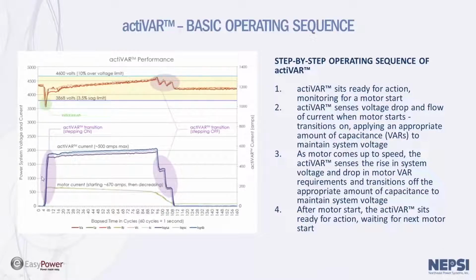The same thing can happen on the front end with a conventionally switched capacitor bank. During the initial starting period, the voltage sag can last up to 5 to 10 cycles because of the speed of a breaker or the speed of a switch. The actiVAR uses a special control algorithm such that it can be turned on within about 1.1 cycles max for the slowest phase from the period of the start, at the time where it starts.